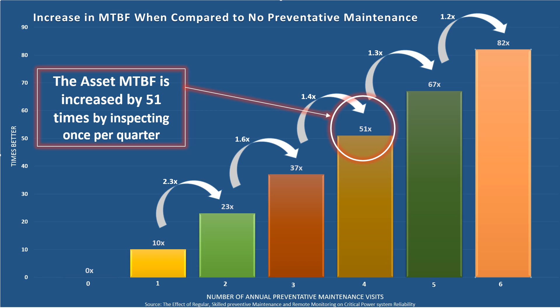To summarize what we've gone through, the use of electrical maintenance safety devices in these surveillance strategies provides real benefits. We remove the high-risk behaviors associated with open-panel energized inspections of electrical assets by maintaining what NFPA classes as an enclosed and guarded condition at all times during the inspection. That means the workforce or inspectors are never exposed to energized components, removing the risk of arc flash or electrocution by contact.